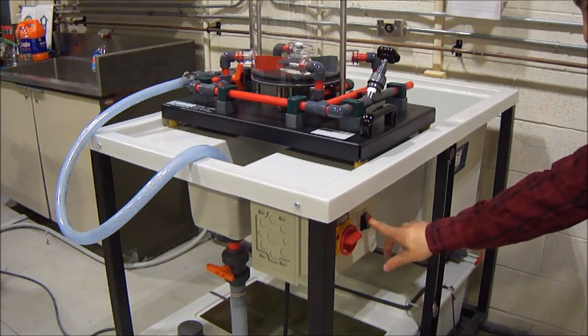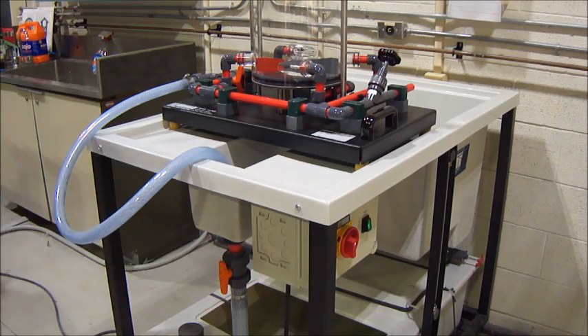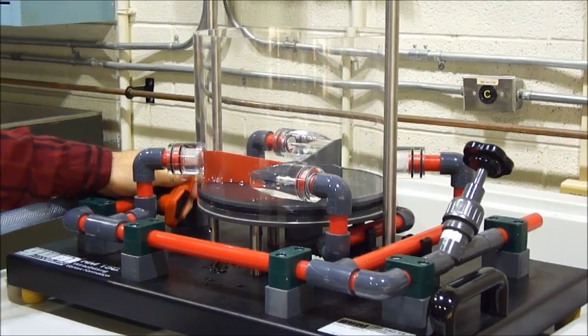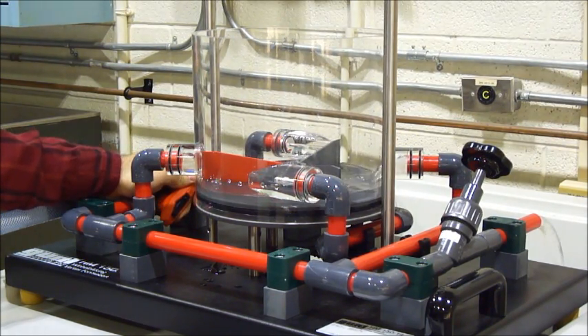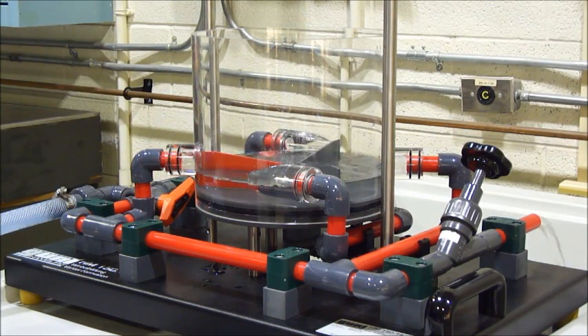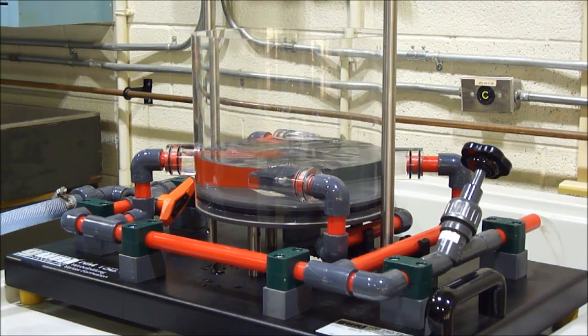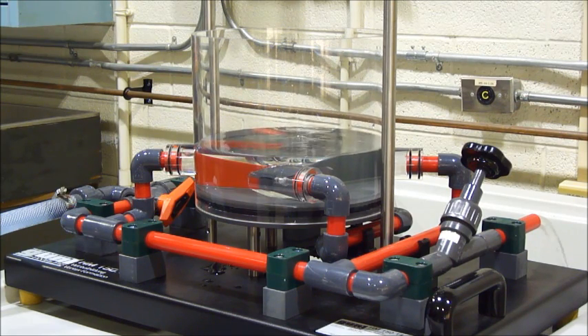Now turn on the power switch and turn on the pump. Open the gate valve, and slowly start to turn the selector valve in the clockwise direction, approximately an eighth of a turn so that the flow gently enters in the radial direction to fill the vessel. Turning the valve a quarter turn such that it is horizontal opens the valve completely. Filling the vessel first with the flow directed radially reduces the quantity of spray on the user.